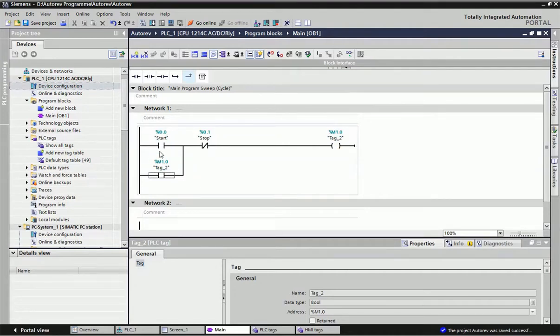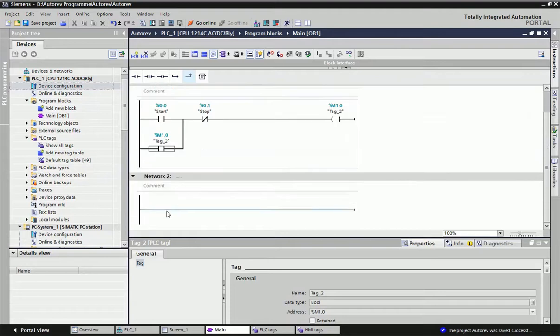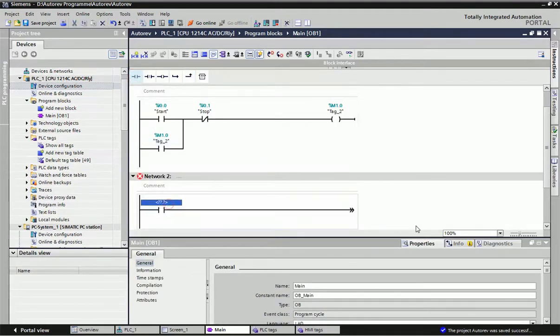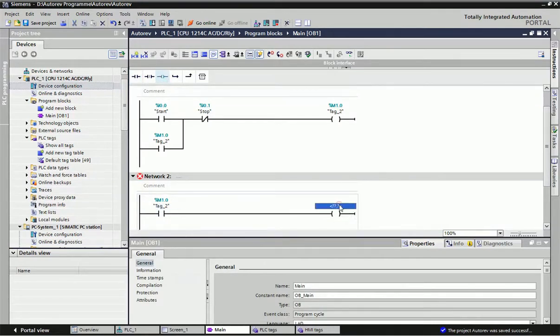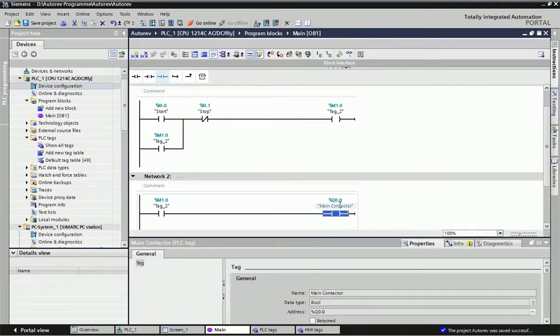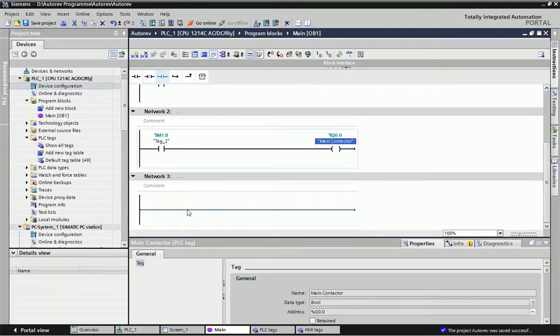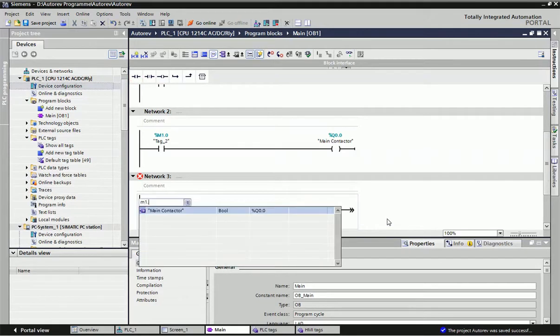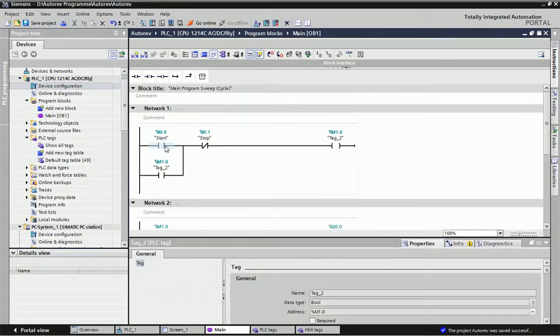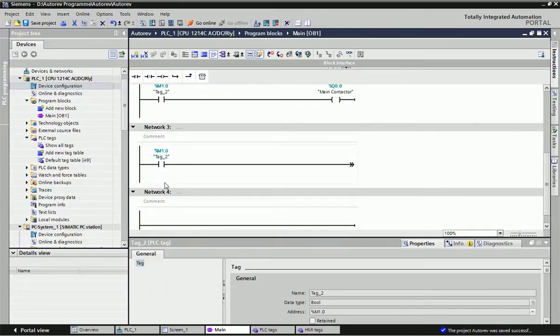When the start push button gives a pulse, M1.0 will be latched and will give a signal. The same M1.0 can be used as a reference normally-open contact. So from the start button I0.0, we can enable M1.0, and the same memory bit can be used multiple times. This makes it very easy for troubleshooting and diagnosis, because you don't need to rewrite the start/stop logic every time.